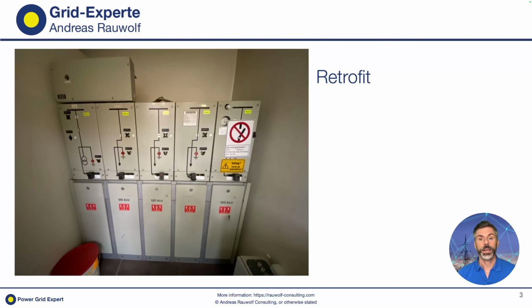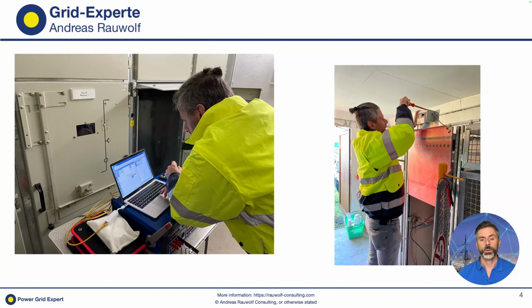Here we can see a classic secondary substation with a medium voltage switchgear, and we want to equip that substation. We want to modernize it with modern measurement technology, with modern fault detection technology. And this is exactly what I'm doing. I'm having a look at the old substation and I'm giving a recommendation how to equip them to be prepared for the future of our grids. And as you can see, I'm also doing the installation, the putting into service and testing.